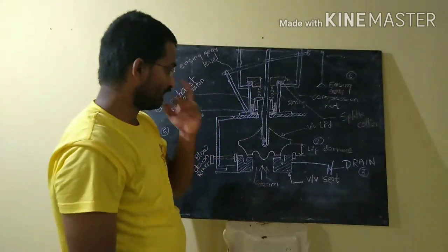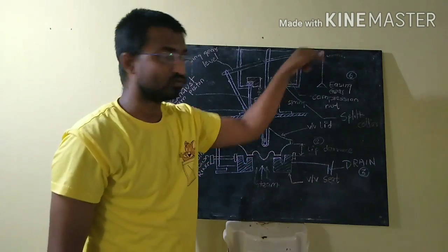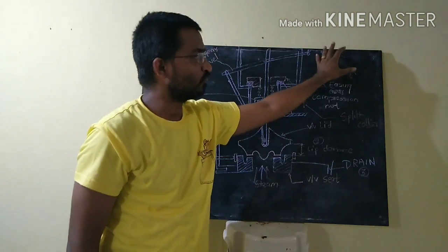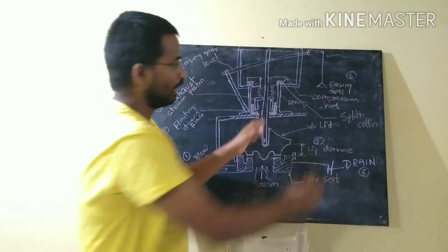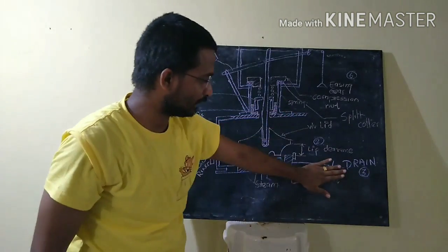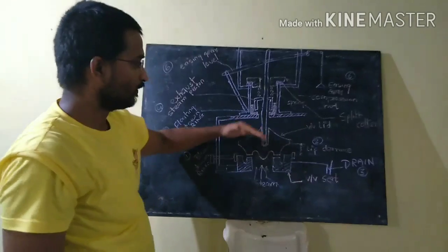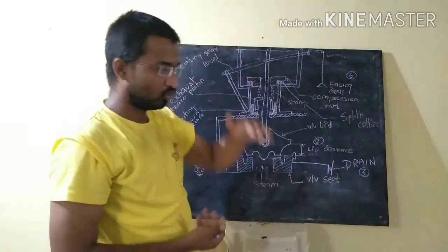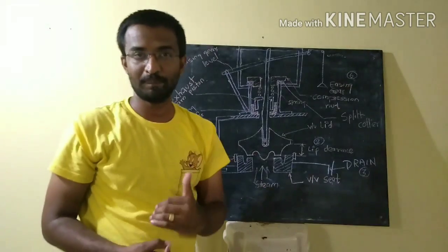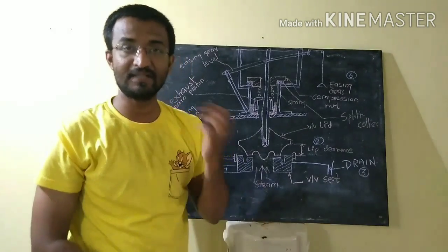When the safety valve lifts, the steam will go outside, and when it sits, the steam inside will get condensed and all the water from the pipe will come back, and if there is no drain, all the water will be on the lid. So now water is there and the spring pressure is there, so your opening pressure will vary, it will increase.